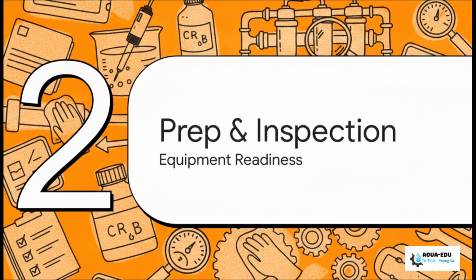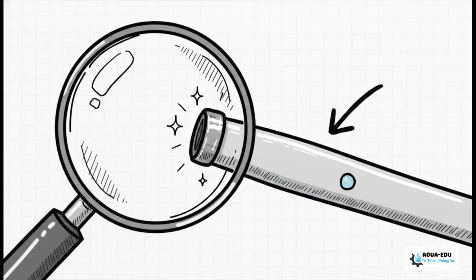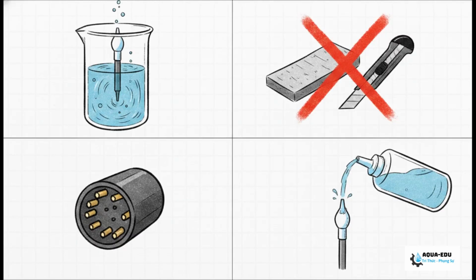Moving right along to phase 2, preparation and inspection. Okay, I want you to get a really bright light and look closely at that platinum ring. It has to be shiny and metallic. It absolutely cannot be dull, black, or coated with any weird oil, protein, or tar. While you're at it, take a good look at the ceramic reference junction to make sure it isn't dried out or clogged up. Now, if you do find that the platinum surface is gunked up, you'll need to soak it in a 1 molar hydrochloric acid solution for about 15 to 30 minutes.